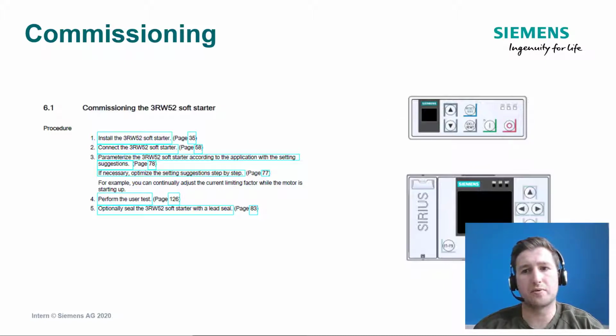It'll give you an error code on this one, or it'll give you a text line display of what the error is on the more advanced HMI. So I would highly recommend that you use either a basic or an advanced HMI. At least purchase one of these for commissioning your soft starters. You can swap that and take it with you into each of the soft starters that you're programming. You don't have to keep it in one device. You can constantly use it in each of the devices which you're commissioning. But just to make things easier for fault identification purposes, using one of these HMIs is a godsend.